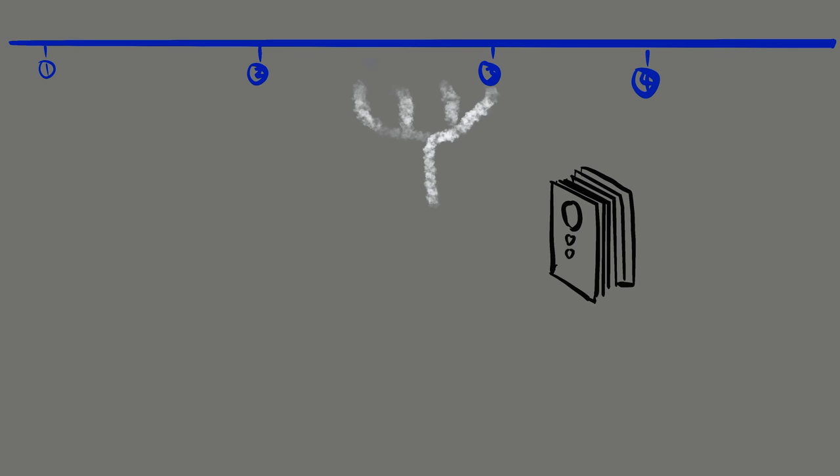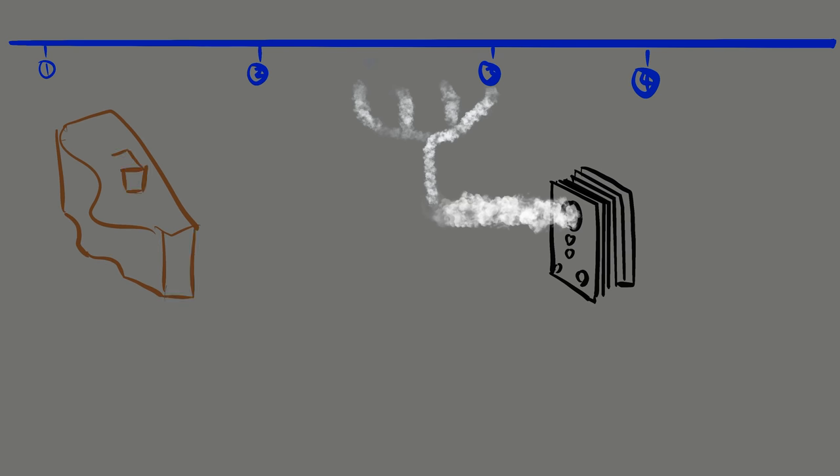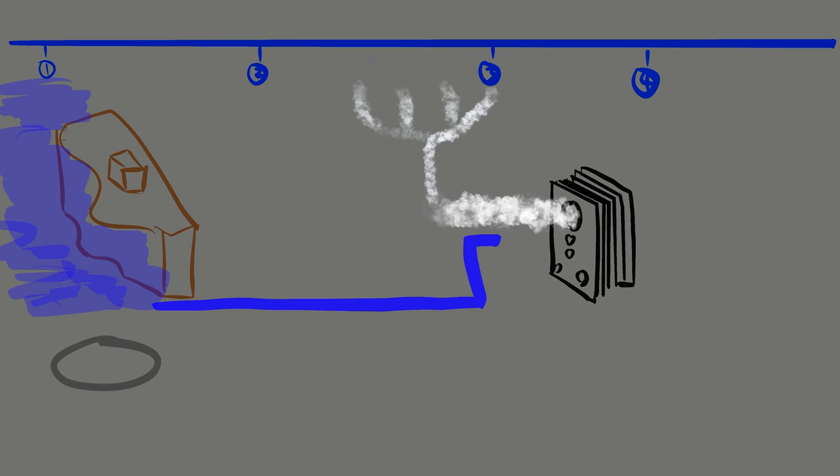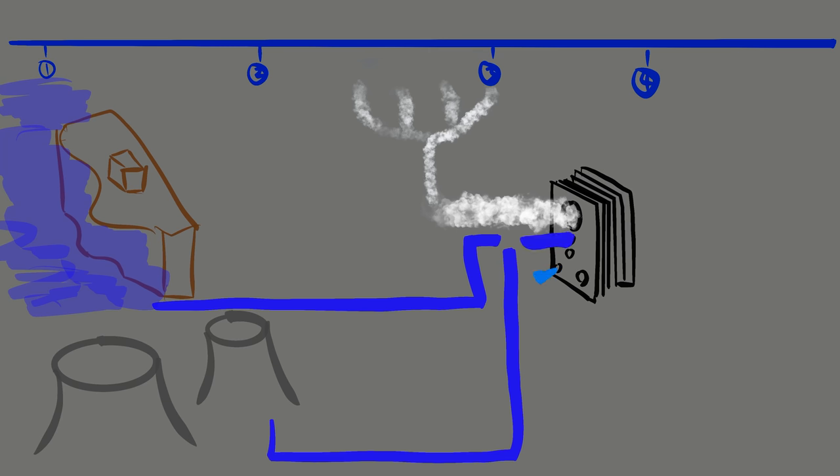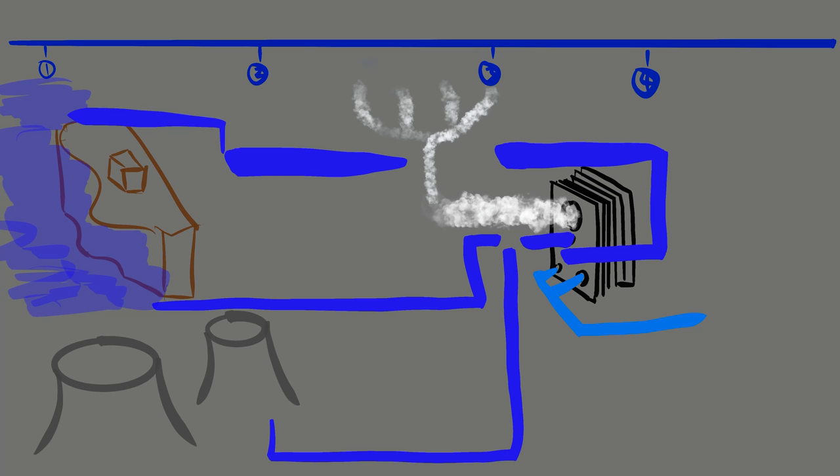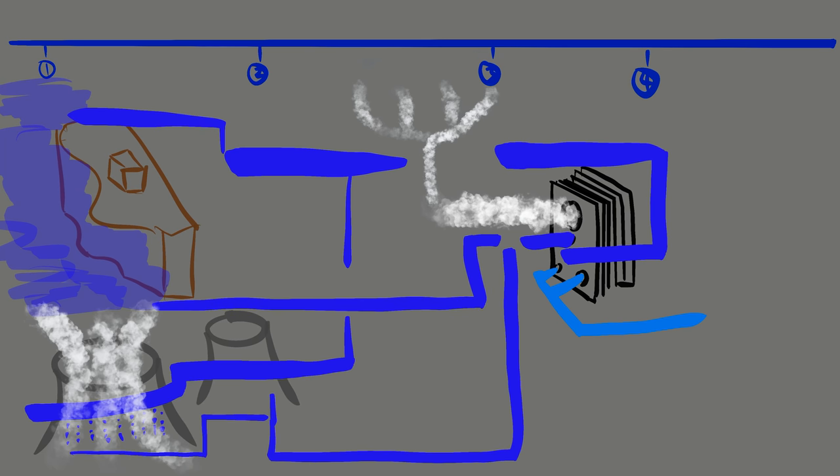The other side of the condenser will either connect to a one-time water through system such as seawater, or a circulating system consisting of cooling towers. Either way, the water will condense the steam and it can pass back to the reaction core to be heated again. And the cooling water, if one time through, will be released into the environment. Or if used with a cooling tower, the water will be sprayed down from the cooling tower, where natural airflow will cool down the sprayed water so it can be cycled again.